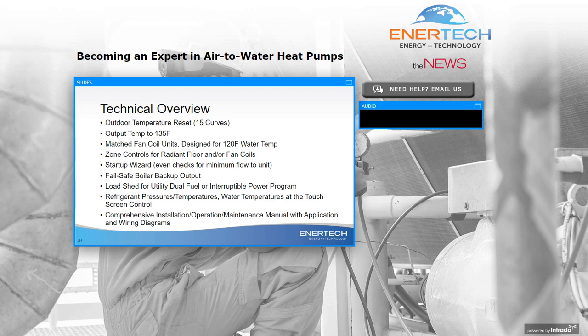Zone controls are available for both radiant floor and fan coils. There's a really nice startup wizard. As you start up the unit on the touchscreen display, it will check, make sure everything is working, and even checks to make sure that there's minimum flow provided to the unit. So if it's not seeing the minimum flow requirement, it won't let that startup wizard go further. There's a really nice fail-safe for boiler backup. If for some reason a pump fails or something else happens, the boiler is the default output. So we're not in a situation where they have no heat.